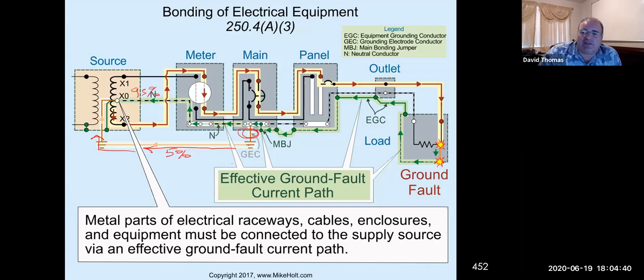Like this one here, say you're going to change the main panel, or you start taking wires out because you're going to change the main panel. If you have any electrical current flowing through this thing, you literally could get killed by removing this wire. And that would be if somebody wired something improperly. They tied the neutral to it. It would not trip the breaker, but it would cause current to flow on the equipment ground, okay?